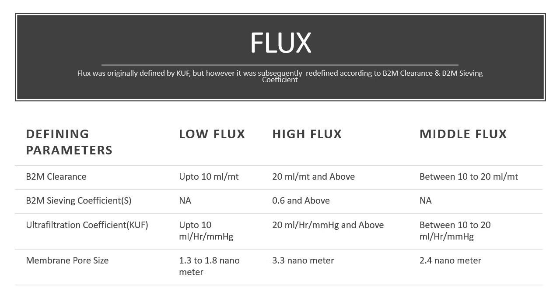There is also a middle flux category. Middle flux dialyzers have a beta-2 microglobulin clearance between 10 and 20 ml per minute; beta-2 microglobulin cannot be removed effectively by a middle flux dialyzer. Their ultrafiltration coefficient falls between 10 and 20 ml/hr/mmHg, and they have a median pore size of approximately 2.4 nanometers.